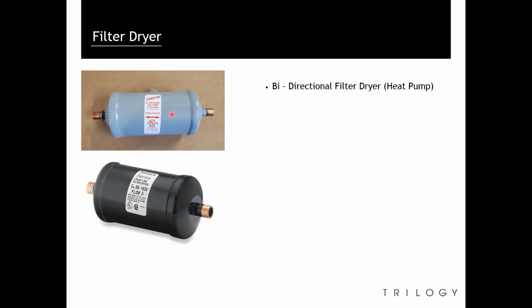Our filter dryers. This is a bi-directional filter dryer. This is for a heat pump application. It will flow through both sides. This is a liquid line filter dryer. This is for condenser only. You see the flow goes towards the house, so towards the indoor. Always make sure the arrow is towards the indoor.